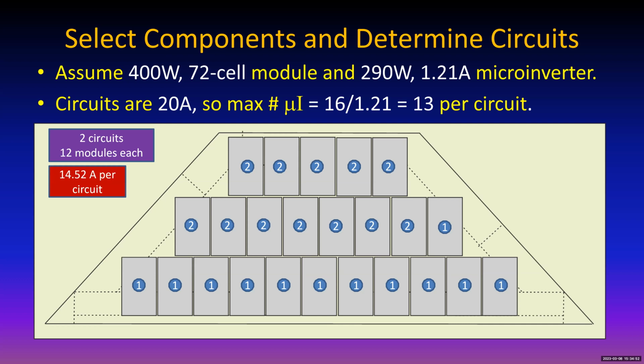And that means that each circuit's going to be 14.52 amps because we get 1.21. This is maximum now. Normally, it's going to be running less than that, but this is the max. So that's certainly within the 16 amp limit. And it might have been, see, what we could have done is we could have just put that number 1 in the middle row, could have been a 2. And it simply would have meant we have 11 and 13. And that's still okay.